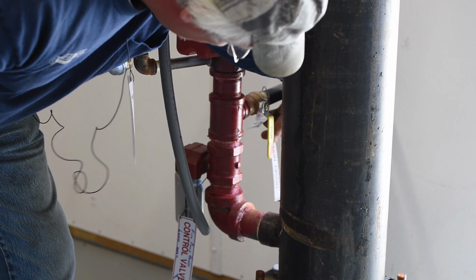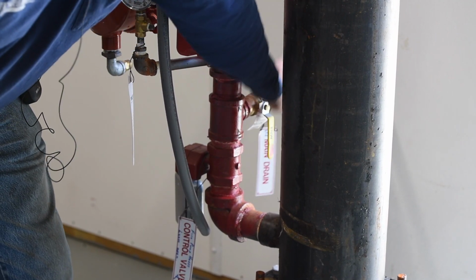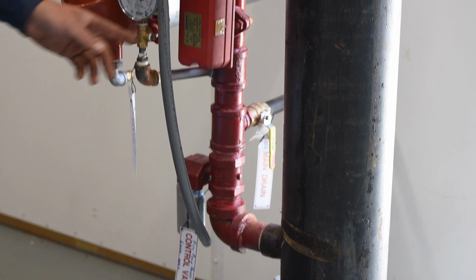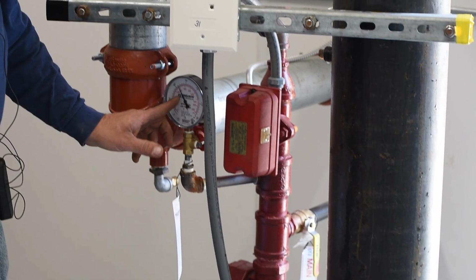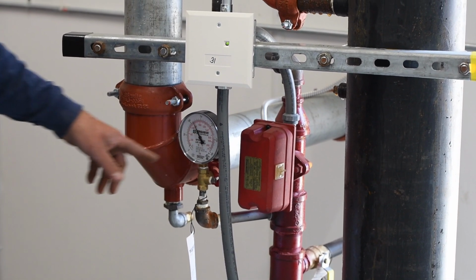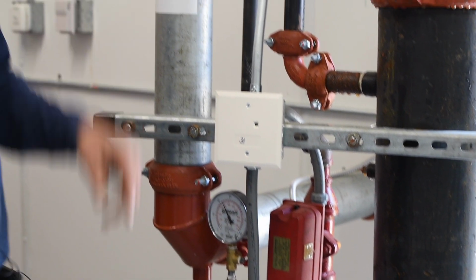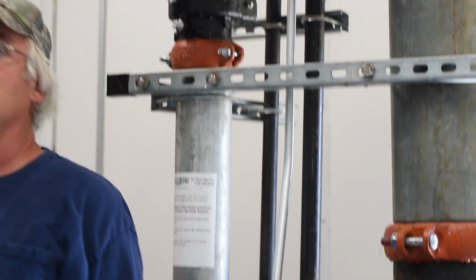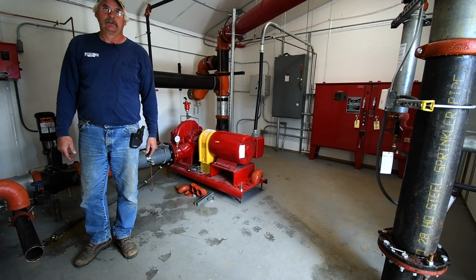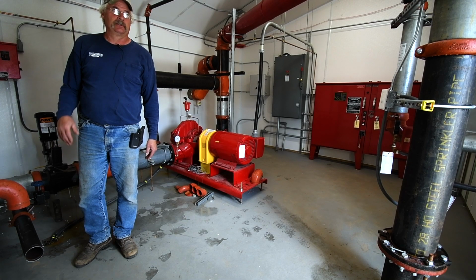The second one up is tagged drain. Okay, that's just piped to the outside. The system comes up, there's a flow switch, a gauge which shows the pressure on the system always. It goes up to the sprinkler system in the pump house. So there's 3 steps to the sprinkler system.